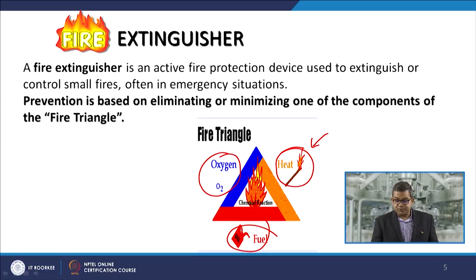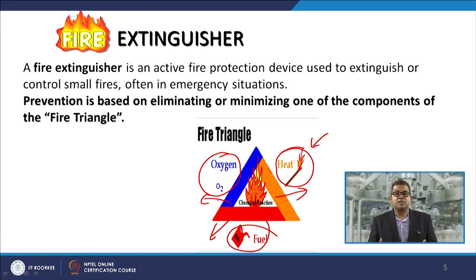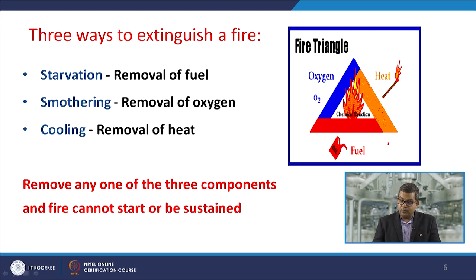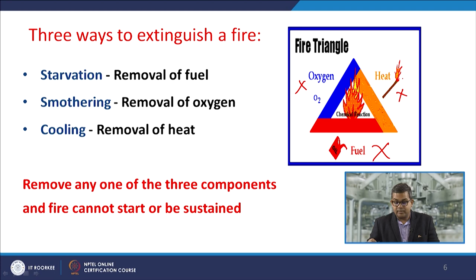Conversely, if you wish to extinguish the fire, you need to disable the fire triangle — either by blanketing it so the supply of oxygen is cut off, by cutting off the supply of fuel, or by removing the excess heat being liberated. So fire extinguishment can be achieved in three ways: starvation (remove the fuel supply), smothering (remove the oxygen supply), and cooling (remove the excess heat). Remove any one of these three components and the fire cannot be sustained.